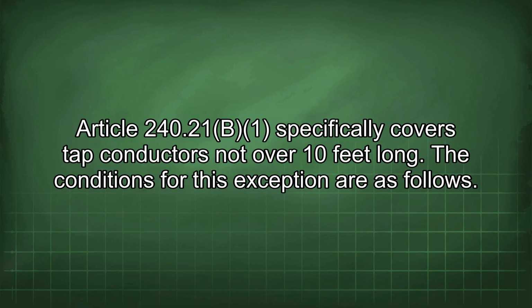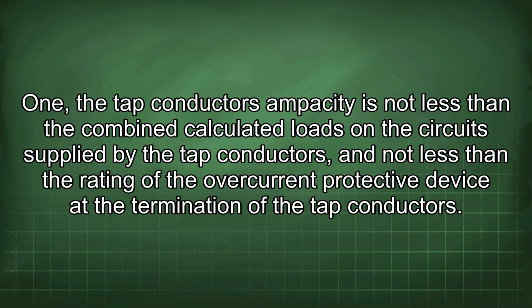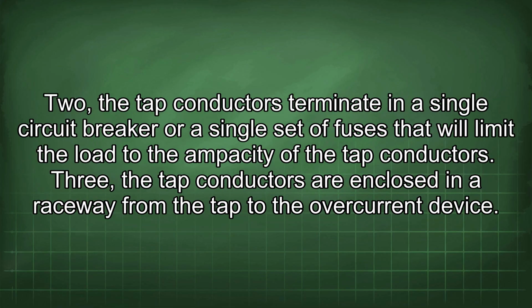The conditions for this exception are as follows. 1. The tap conductor's ampacity is not less than the combined calculated loads on the circuits supplied by the tap conductors, and not less than the rating of the overcurrent protective device at the termination of the tap conductors. 2. The tap conductors terminate in a single circuit breaker or a single set of fuses that will limit the load to the ampacity of the tap conductors. 3. The tap conductors are enclosed in a raceway from the tap to the overcurrent device.